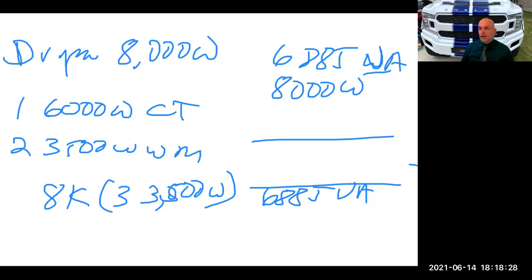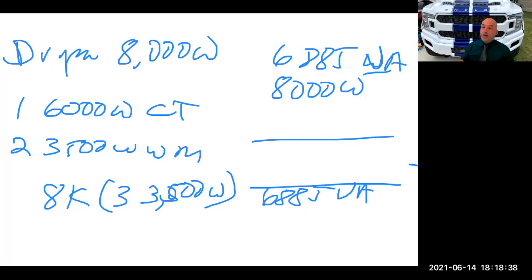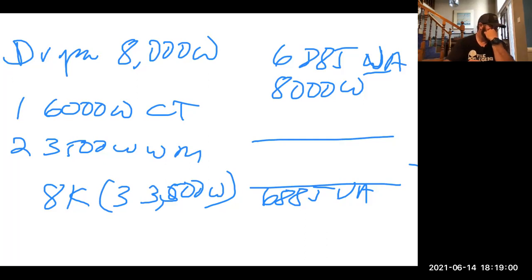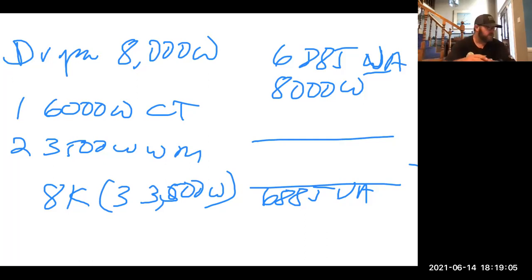Right. So each one of these you can't combine and shift columns. They are what they are. You got to leave them in their columns. You got to process them all the way out. Now note 3 may come into play because if they're unequal ratings or whatever. But be careful of that cooktop and the wall mount business whenever you're doing service calculation, because it's really completely irrelevant. It would only apply if you're doing a branch, and then there could only be 3, and that's a cooktop and up to 2 wall mounts. And it sounds like you had 4 or maybe some other mix. So it didn't really matter what they are. You just got to find out what column they fit in at face value and run them through their respective columns.